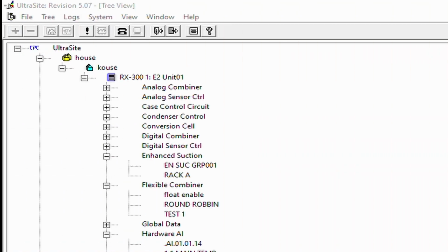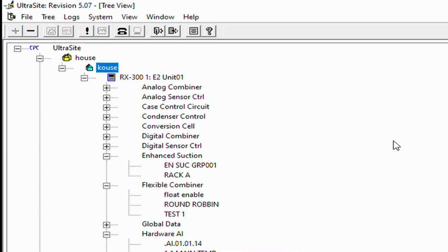All right, guys, welcome to another Advanced Refrigeration podcast training on the E2 controller. Today, we're going to be going over the send-to function and how to set up log groups for multiple points at once. So first things first, what you're going to do is log into the controller. We're already logged in, and make sure you're logged in with a level 4 password.